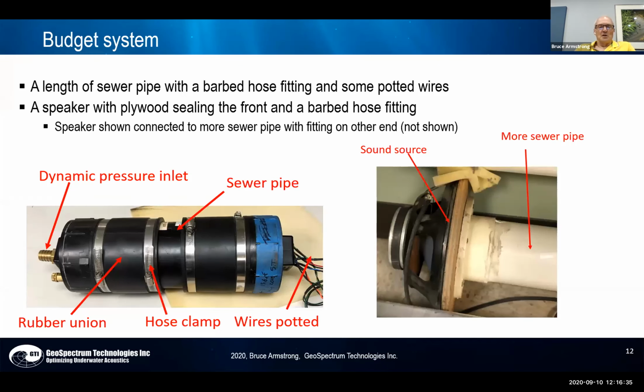So here is your budget calibration system, and this is actually one that we use. It looks crappy, but it works just fine, and you make it out of a sewer pipe. So you've got a length of sewer pipe, you've got some rubber unions that join sewer caps. At one end of the sewer pipe, you have a dynamic pressure inlet, and at the other, you have some wires that you pass your signal leads out of the sewer pipe.